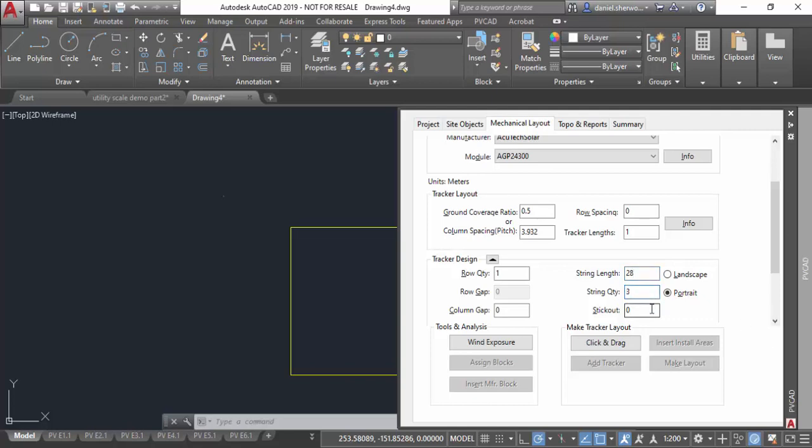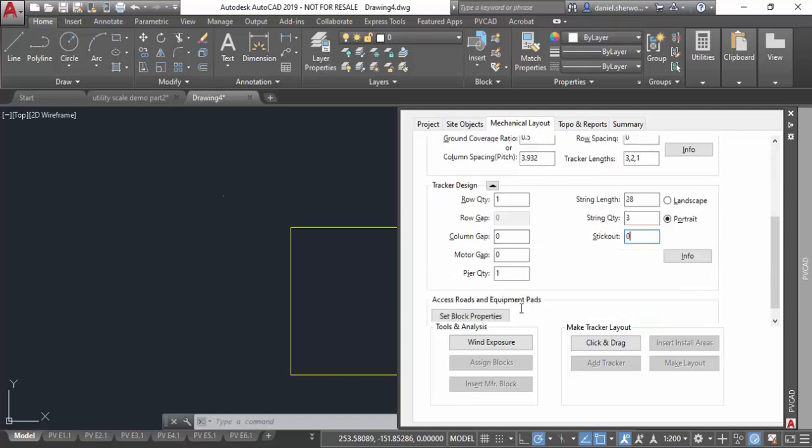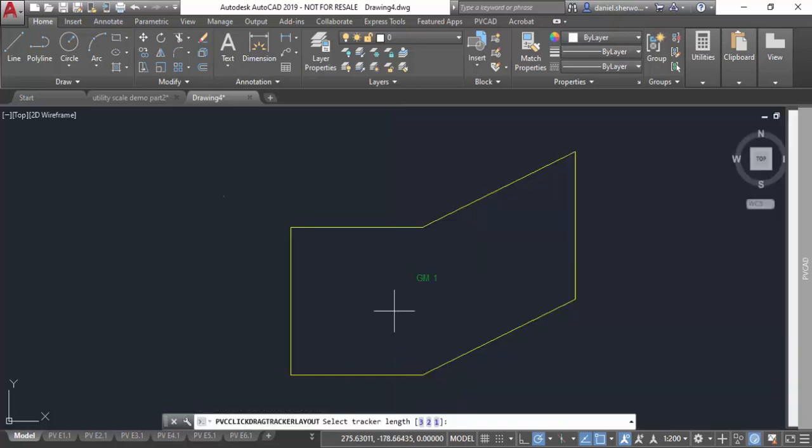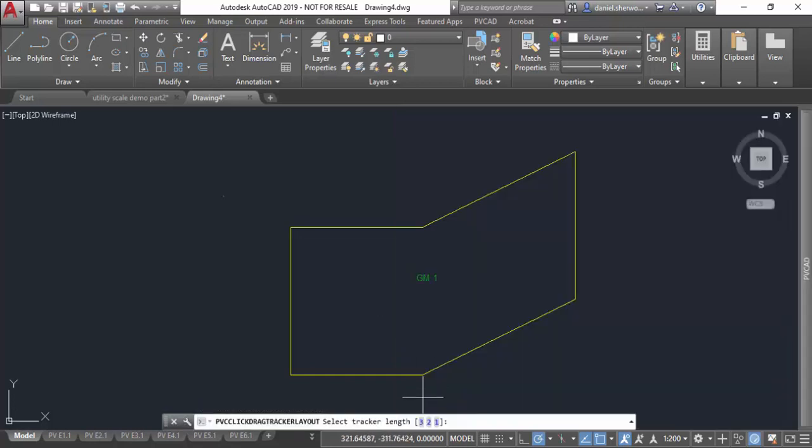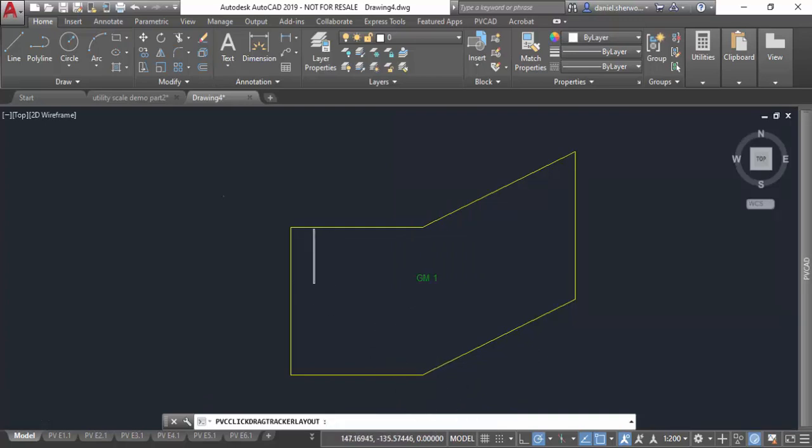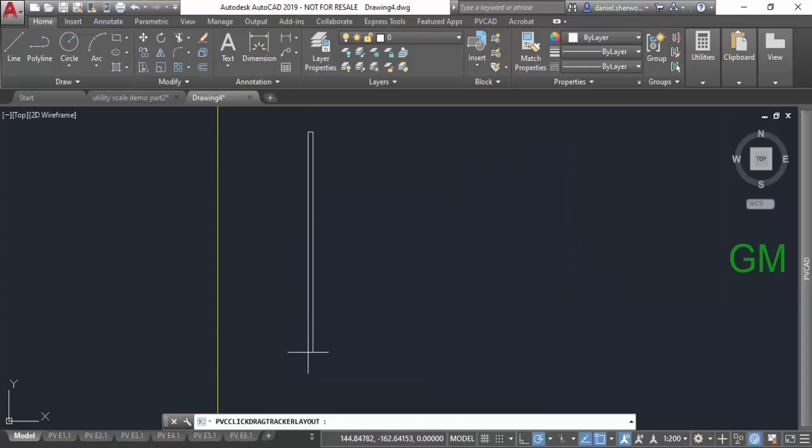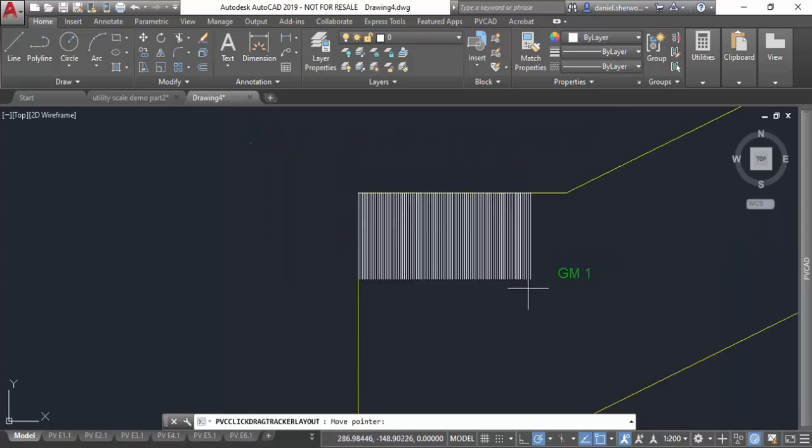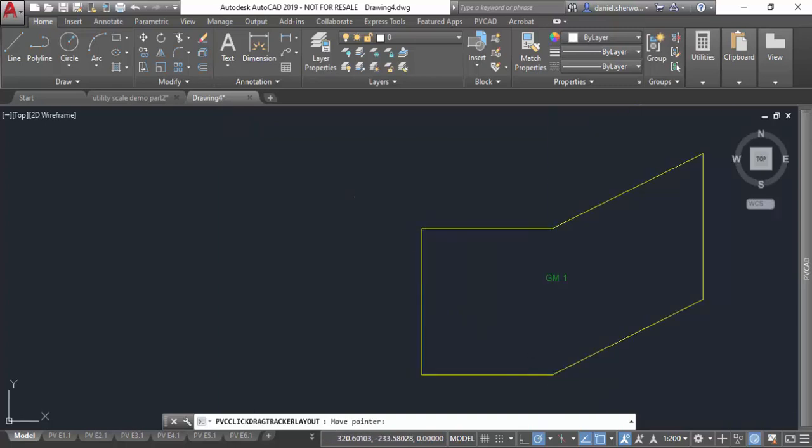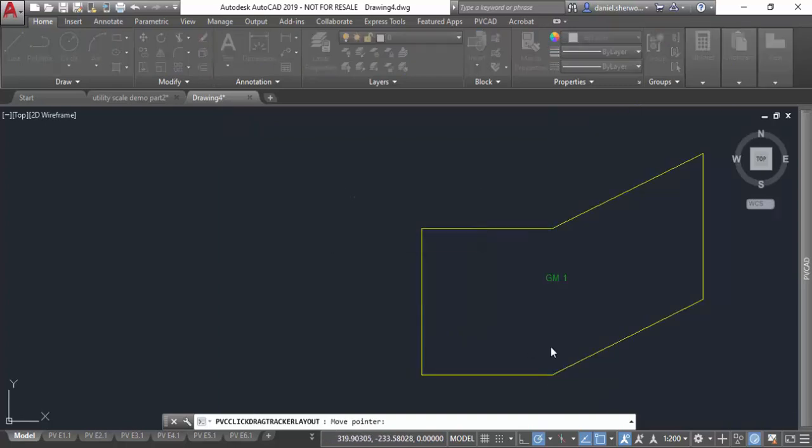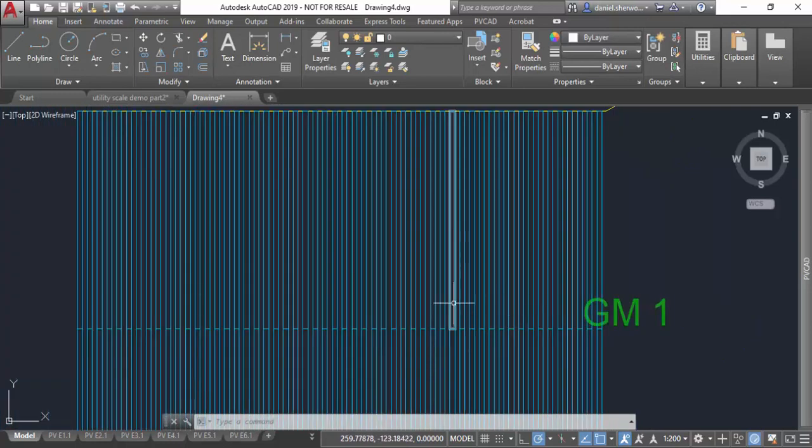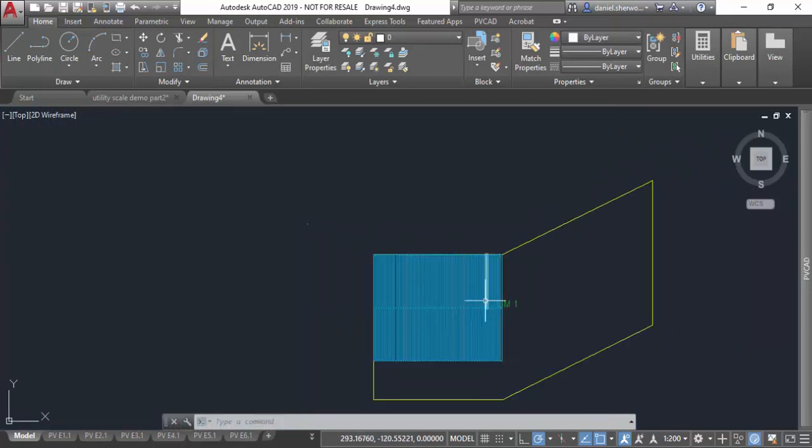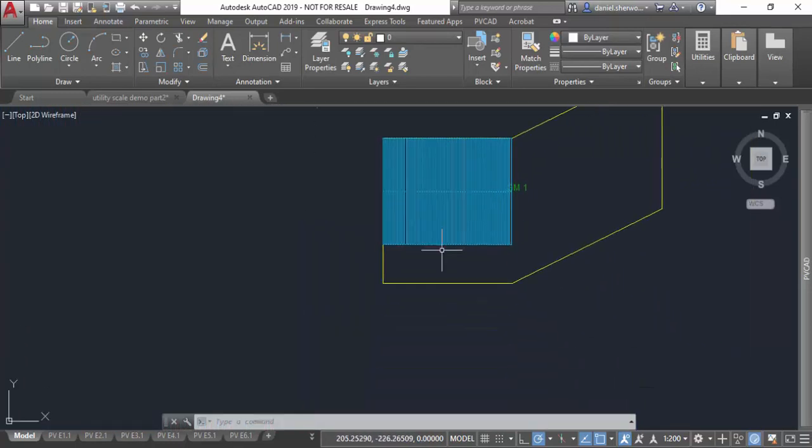Now I'm going to do another example. I'm going to use user-defined, which means I'm going to specify some more boxes where I put in my string length and the number of strings per tracker and how much trackers stick out past the end of the last module and column gaps and things like this, just to define the geometry that otherwise comes preloaded when I pick NextTracker. Then I'm going to use the click-and-drag feature to insert my trackers. The first thing it'll ask you is what length of tracker you want to insert, whether it's the full three-string tracker or partial tracker. Then it'll ask you what angle to use, and here I'm just going to use a default angle which is just a square array, not an angled layout. I can then use the shift-tab key to take my insertion point and then drag out using click-and-drag an area of trackers.